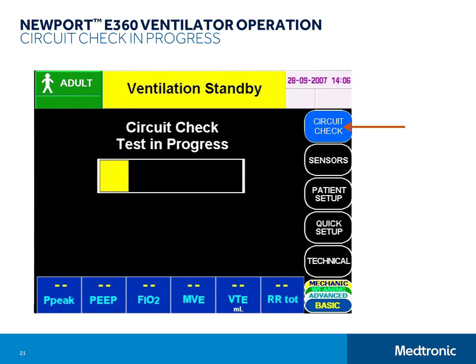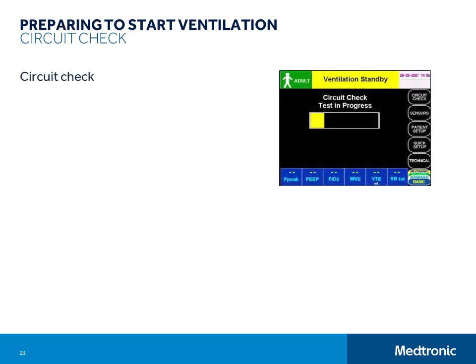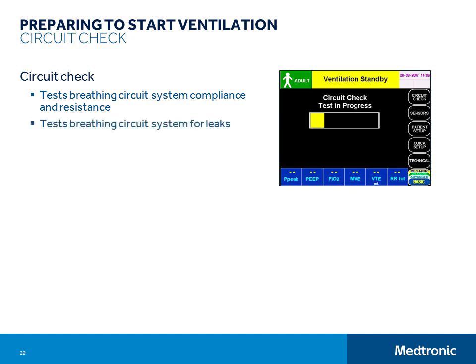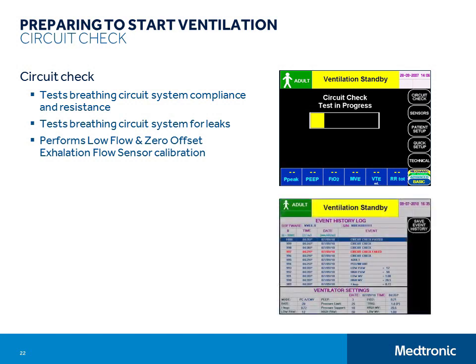This quick automated function tests the breathing circuit system compliance and resistance, tests the breathing circuit system for leaks, and performs both a low flow and zero offset exhalation flow sensor calibration. The pass or fail result of the circuit check is logged in the event history. Always remember that you will get the best results from the circuit check, meaning that the measurements and calibration values will be most accurate, if you fill the humidifier chamber to the fill line, turn the ventilator and humidifier on about 30 minutes before the check, and keep the tubing very still during the circuit check.